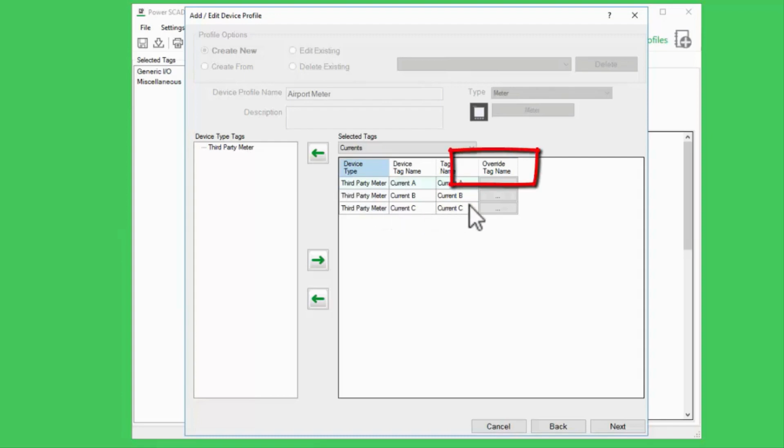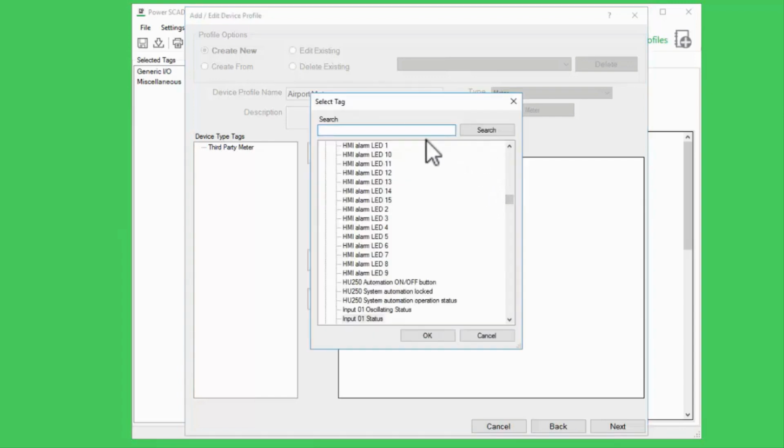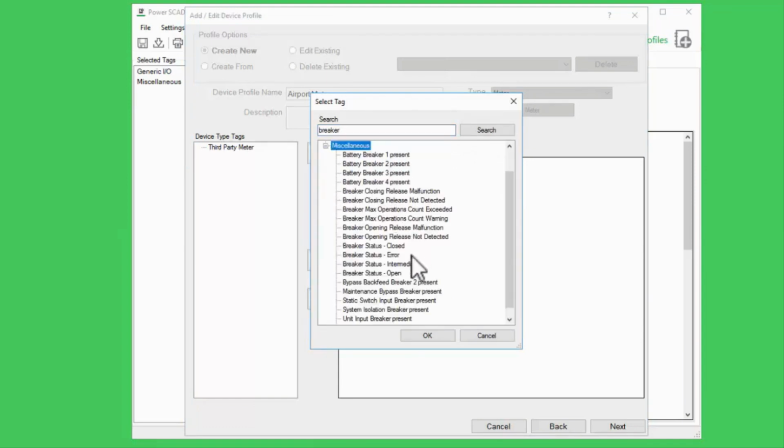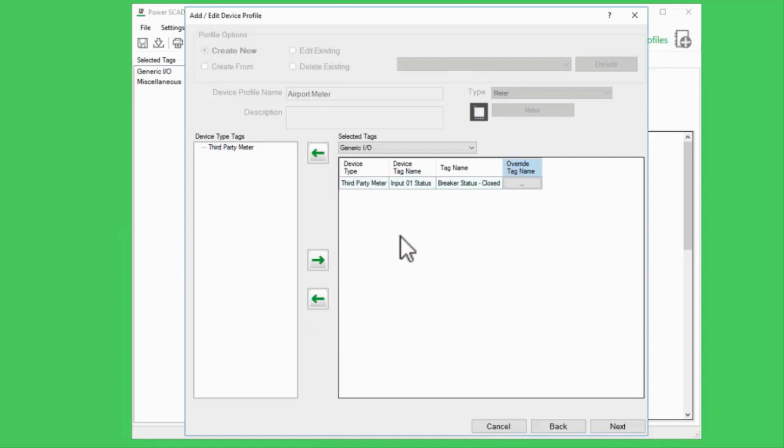Also, note the Override Tag Name button. This allows me to keep the addressing for the tag, but replace its name, IEC tag name, and item name with those of another tag. If I know my meter will always be reading a breaker status on its input, I can change it to that tag.